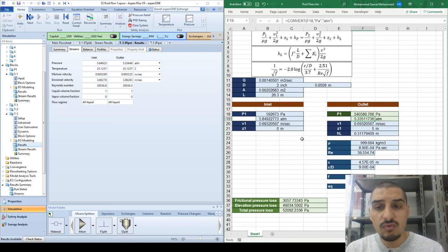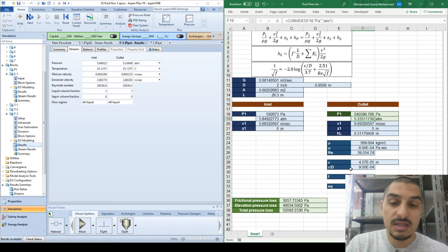You can do the same thing for pipelines. It's going to be just different because in this case, you need to take into consideration that there are two pipes. So you have to put that in the calculations. For the pressure losses, you would have more than one part. You'll split it into different parts and add the total losses for each part. And in case of change in the diameters, then you need to take into account the sudden expansion and sudden contractions, and this is not going to be difficult, but it's going to take more time.